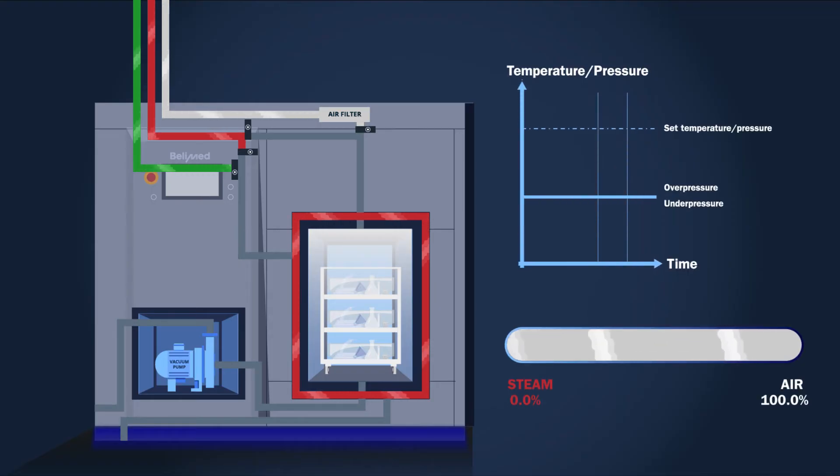Since air is a very good insulator, as much air as possible must be evacuated with the integrated vacuum pump. This happens in several fractions.